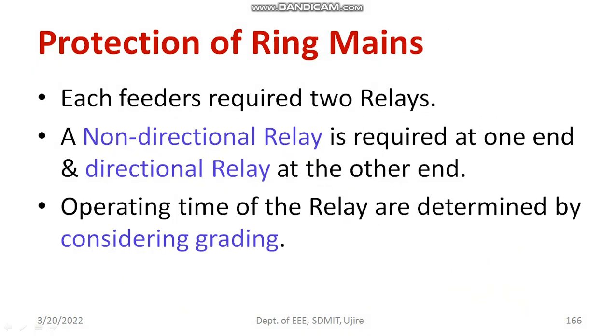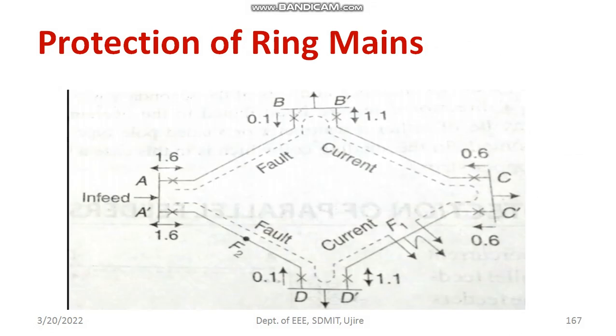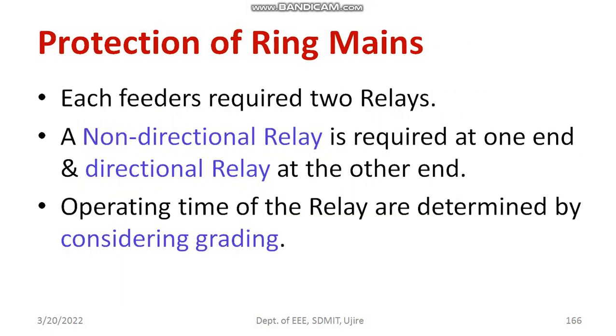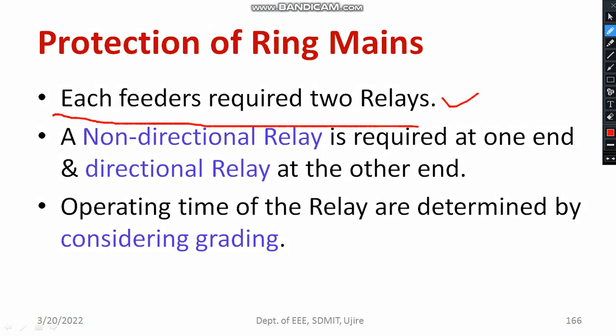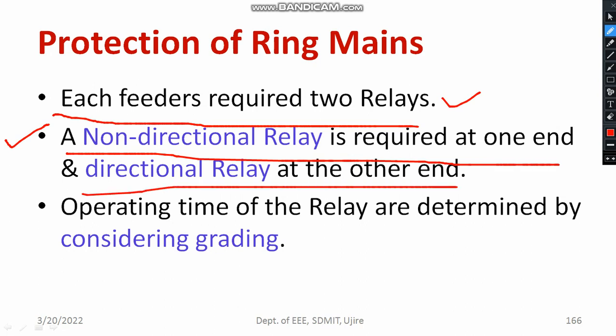Regarding ring mains — ring mains is also a very important segment of the distribution system. If I talk about the distribution system, ring mains, service mains, and feeders are very essential segments. Now how to ensure the protection of ring mains? In ring mains, feeders are included. Each feeder requires two relays — one should be directional and another should be non-directional. A non-directional relay is required at one end and the directional relay is required at the other end. The operating time of the relays is determined by considering what kind of grading is employed. This is the basic information about protection of ring mains.